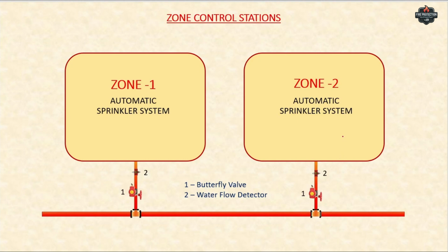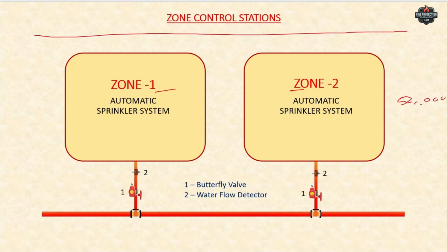Here I am to say, in a basement we have multiple zones. So each zone should have one floor control station. Suppose this is your full basement. Then maybe we have one zone, 2 zones, 3 zones, or 4 zones based on your area. That means one zone can take up to 52,000 square feet of area. In that case for each zone you're supposed to have one butterfly valve, one flow switch, a test and drain valve, which is not shown here, and the pressure gauge for each zone.